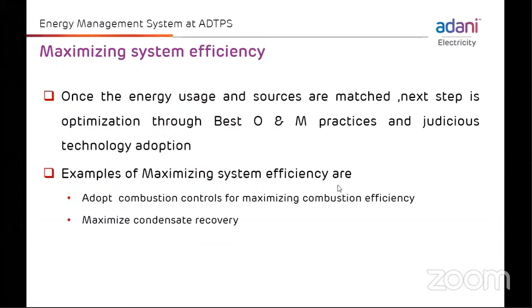So for that, in our case, we have installed one CO analyzer at our chimney, that is at the outlet of the boiler. This CO indicates the type of combustion happening in the boiler, and based on this CO monitoring, we should modulate our air in the boiler.